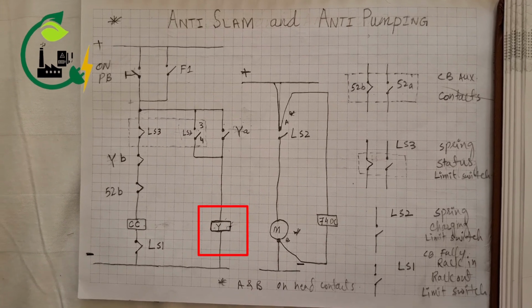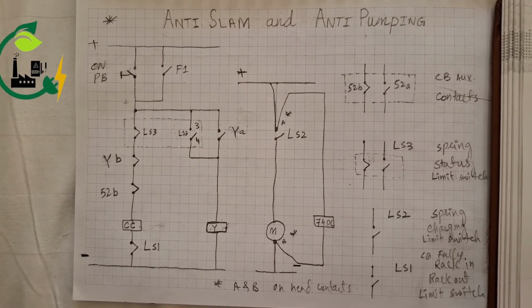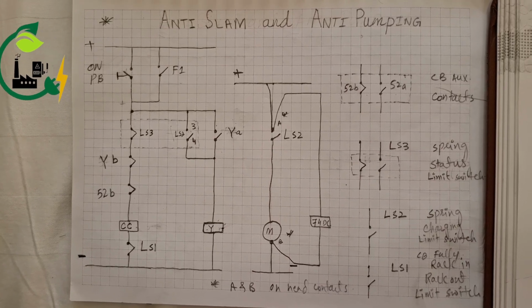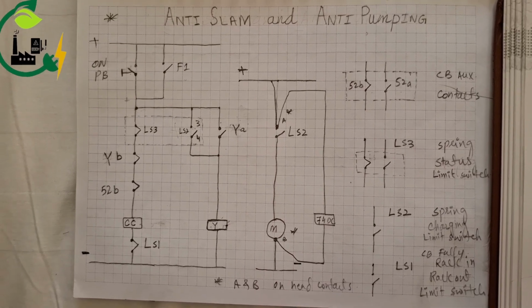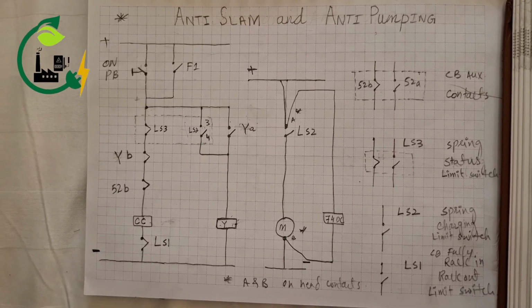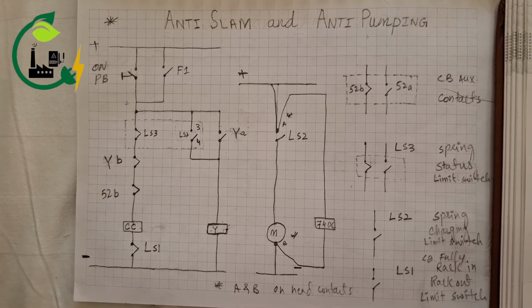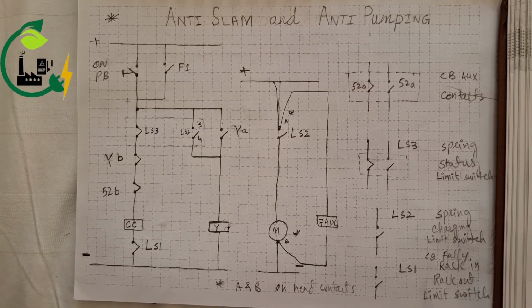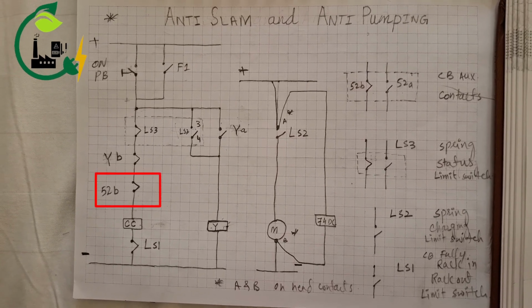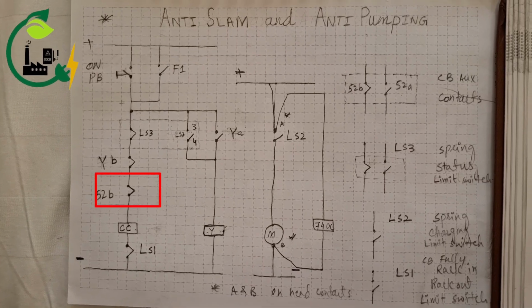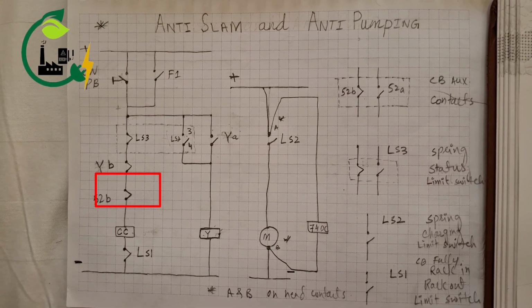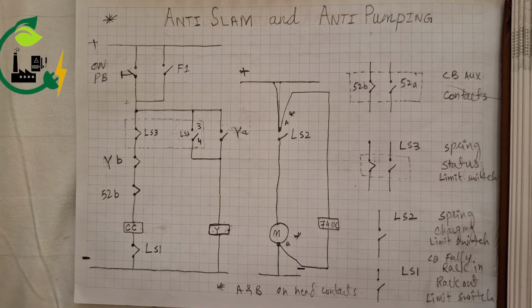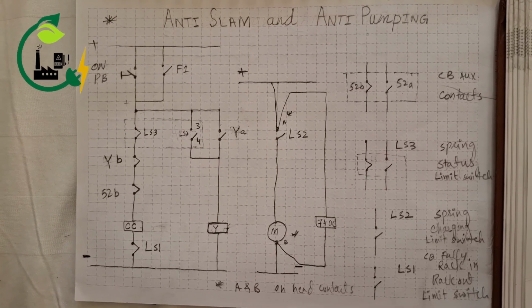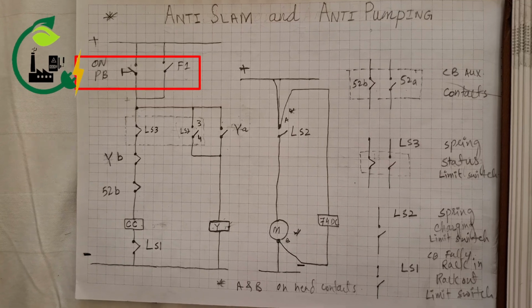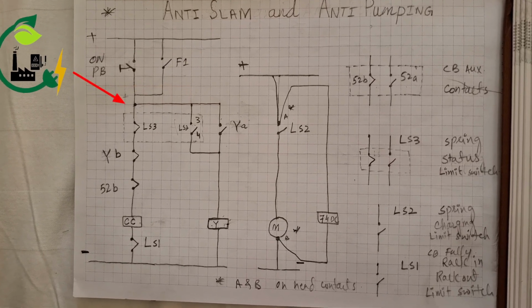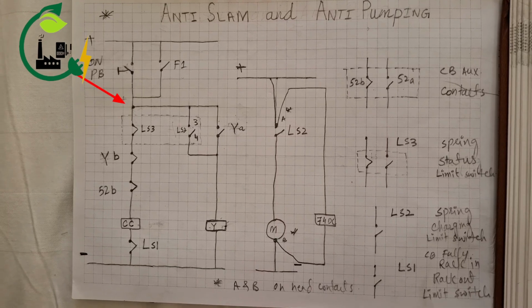Why do we use an anti-pumping relay? What happens if we give a close command to the circuit breaker and the circuit breaker is tripped due to any protection or any fault? If the lockout relay is operated, the tripping coil will be energized in the tripping circuit and the circuit breaker trips. So this 52B will be normally closed again, because the circuit breaker is not closed and has tripped due to protection. So what happens if someone is giving the command, a push button is latched or the BCU contact is latched? Here the positive supply is available in that case.